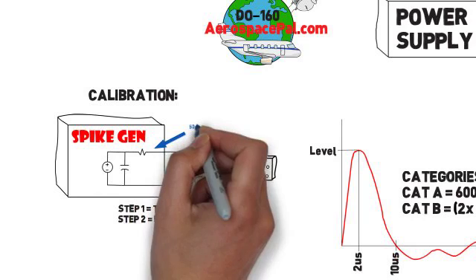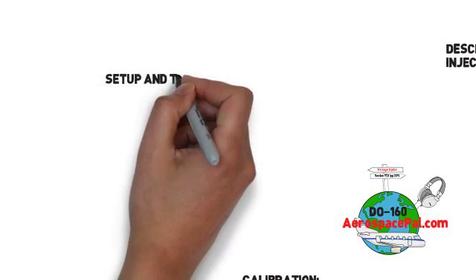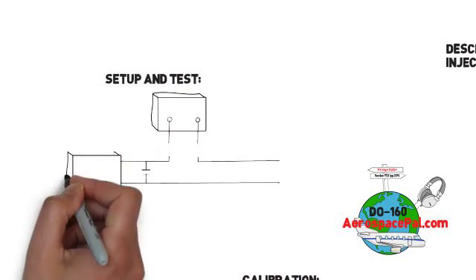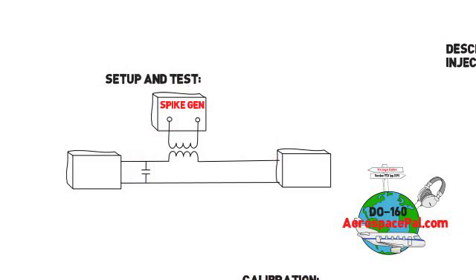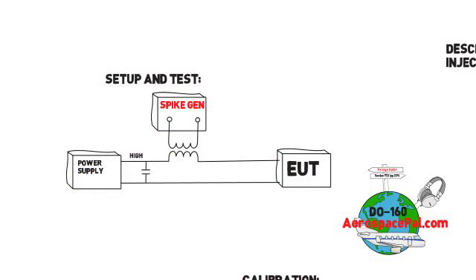Use the test setup shown here, adding an injection transformer in line with the EUT's power line. When testing, apply at least 50 positive pulses in less than a minute using the generator level established during calibration. Then apply 50 negative pulses in less than a minute.